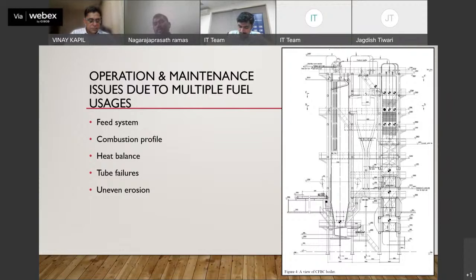But as we fire more biomass having less ash percentage, CFBC boilers need some more ash circulation in the system so that steam generation stays in line and the furnace operating parameters become normal. So we reduced the cyclone inlet opening to increase the cyclone velocity. Earlier the cyclone inlet velocity was 20 meters per second. We increased it up to 25 by reducing the cyclone inlet opening from 1000 mm to 750 mm. After which we got a good observation, and collection efficiency also increased.